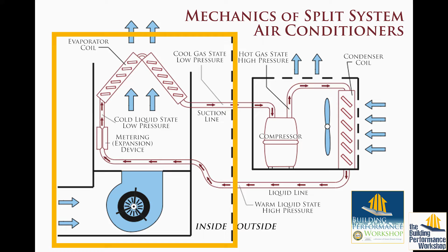You give it warmer air, what's it going to do? Is it going to be better at its job or worse at its job? It's going to be better at its job. It's going to be easier to pull that heat in and send it outside to the magic part outside that gets rid of the heat. So when we say it's going to be 80 degrees in the return and a 67 degree wet bulb, warm wet air tells me that the capacity of this system is 33,600 BTUs. It's a 3-ton system. By the way, that's not already 36,000. It's 33,600.